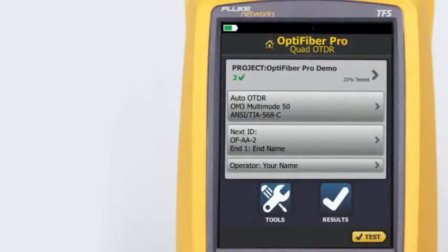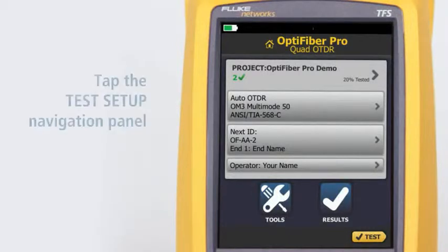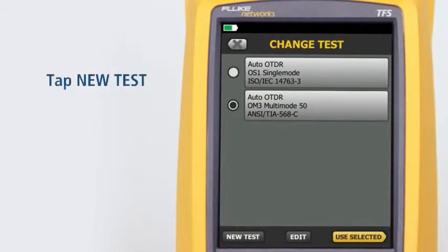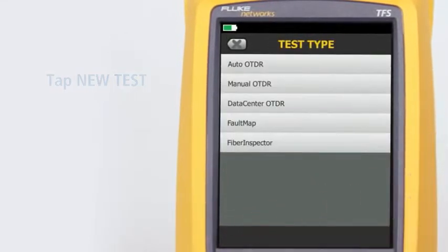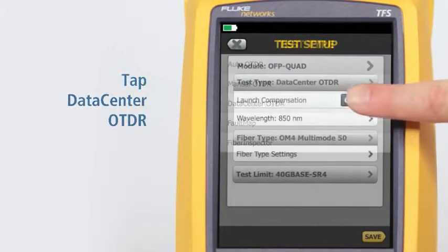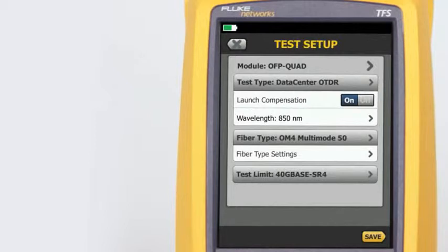The Data Center OTDR test mode is optimized for fiber installations that have short links, many connections, and the possibility of large reflections. Tap the test setup navigation panel, then tap New Test, then tap Data Center OTDR. Note that the Data Center OTDR defaults to only 850 nanometers for multi-mode fiber and 1310 nanometers for single-mode fiber — these are the wavelengths typically used in data centers.